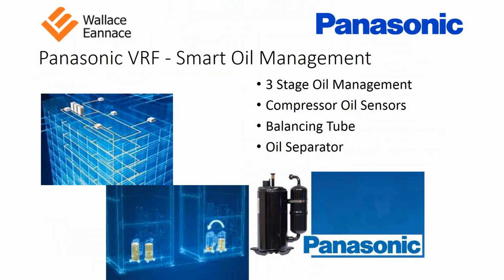And we also use an oil separator. So what our oil separator is, it's like a reservoir, and it's connected to all of our compressors, and it is basically a reservoir for oil to keep. It's basically like a storage tank, okay? And so when the compressor needs oil and we're low, we can also steal oil from this oil separator here. So 3 ways, 3-step, 3-stage oil management. Panasonic VRF takes this very seriously.